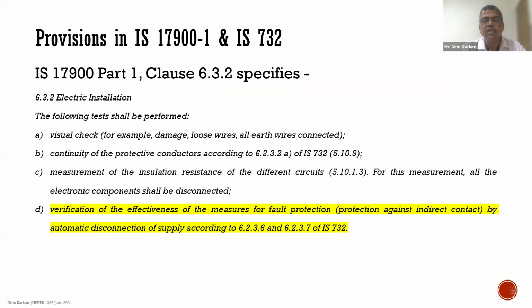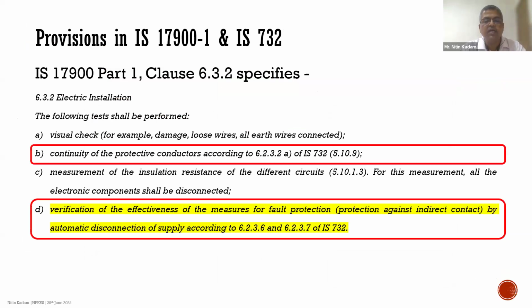So let us see how this is related with IS 732. If you see here, 17900 explicitly specifies clause 6.3.2 B and D, which talks about the continuity of the protective conductors according to 6.2.3.2A of IS 732, which Mr. Gopakumar was also specifying. And then subclause D, which specifies verification of effectiveness of the measures of fault protection, protection against indirect contact by automatic disconnection of supply according to 6.2.3.6 and 6.2.3.7 of IS 732.